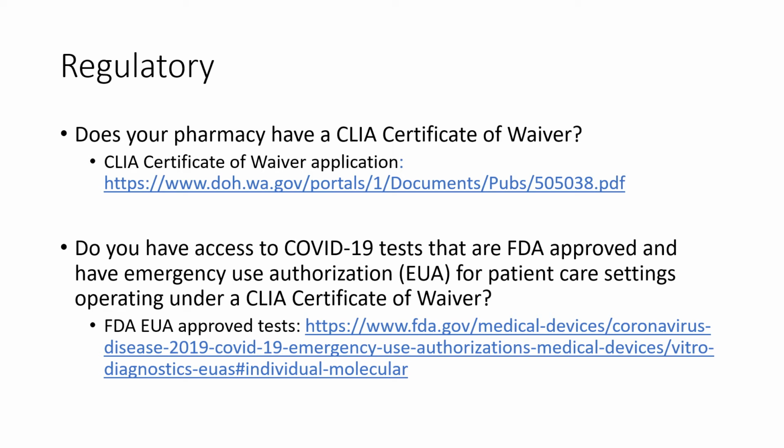If you are performing specimen collection in partnership with a lab, you should be offering a test with an EUA for high and/or moderate complexity settings. If you are performing point-of-care antigen testing, you will be offering a waived test. Waived tests are defined as simple laboratory examinations and procedures that have an insignificant risk of erroneous result. The FDA determines which tests meet these criteria when it reviews manufacturers' applications for test system waiver. Tests that will be run in the pharmacy must be authorized for the CLIA waived setting.